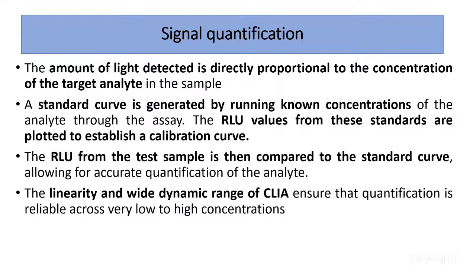And the dynamic range is the scale from this to the limit of detection. To simplify, every assay should have a lower limit of detection and an upper limit of saturation. If you go past the upper limit, where more light is generated and more analyte concentration is indicated, they actually discard it. That's how they maintain the linearity of the reaction.